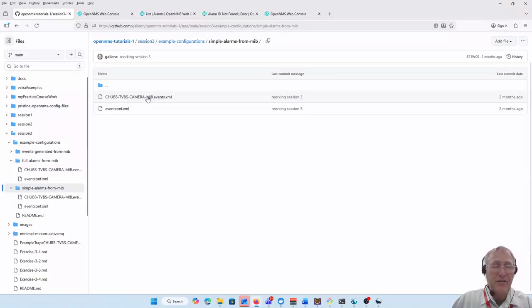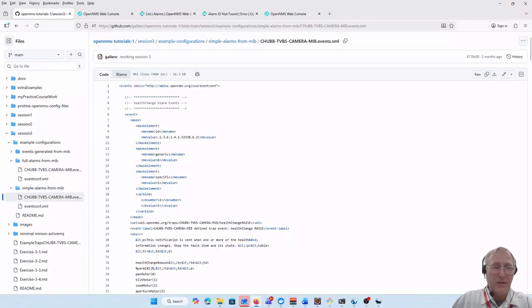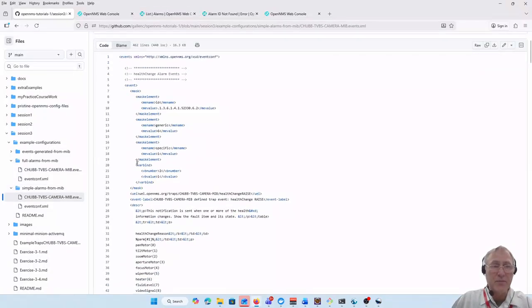And then after that definition of the specific alarm, we would just put in this less specific example that just carries all the rest. But remember that the order in which these are processed is determined by the order in the file. So these simpler definitions of alarm change events would have to go after the specific definition of the events that you'd use from the other example.